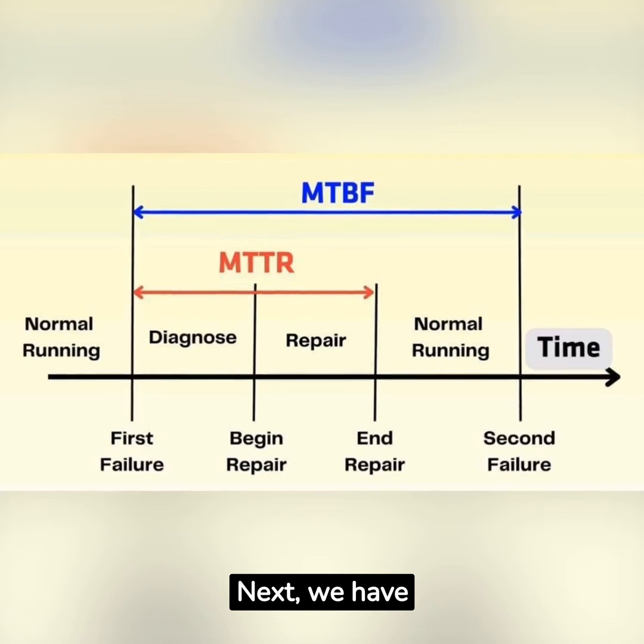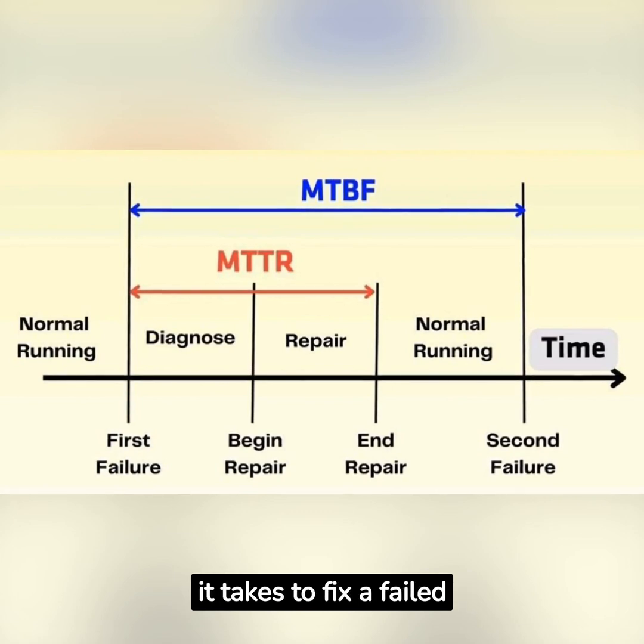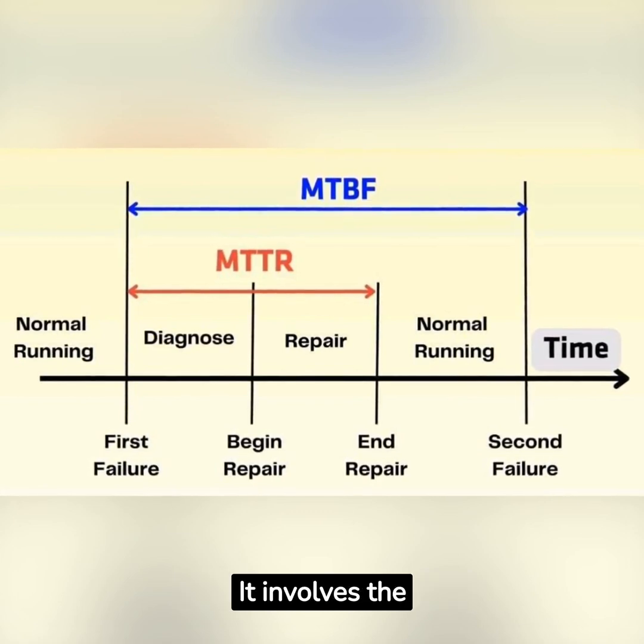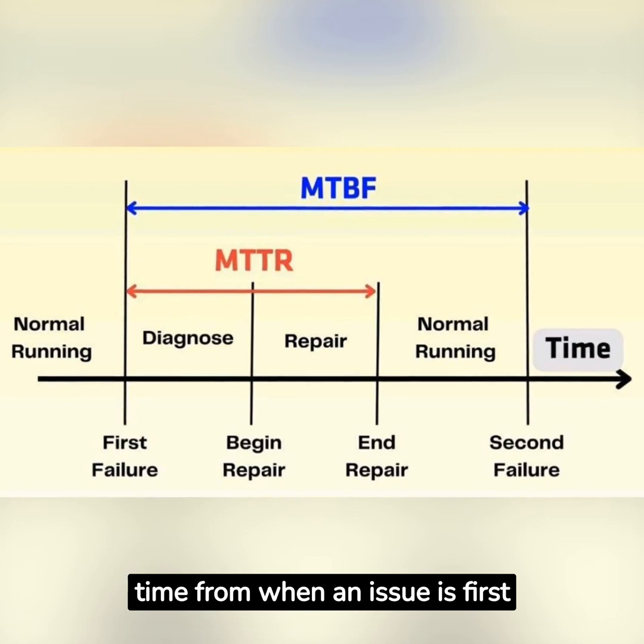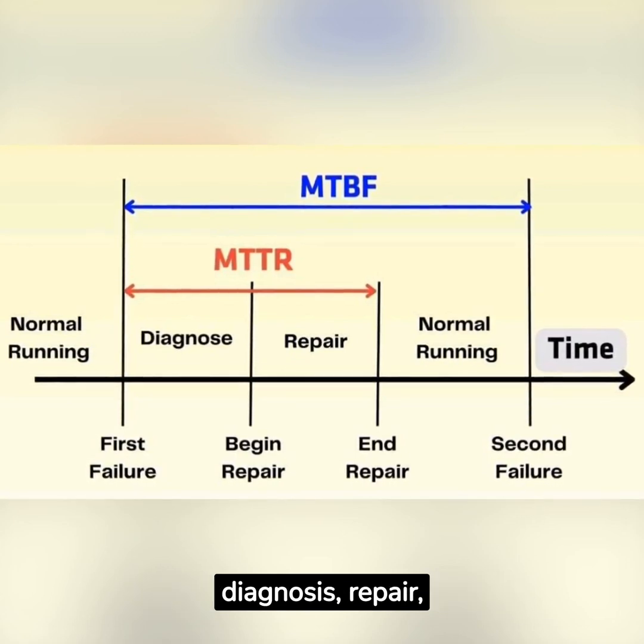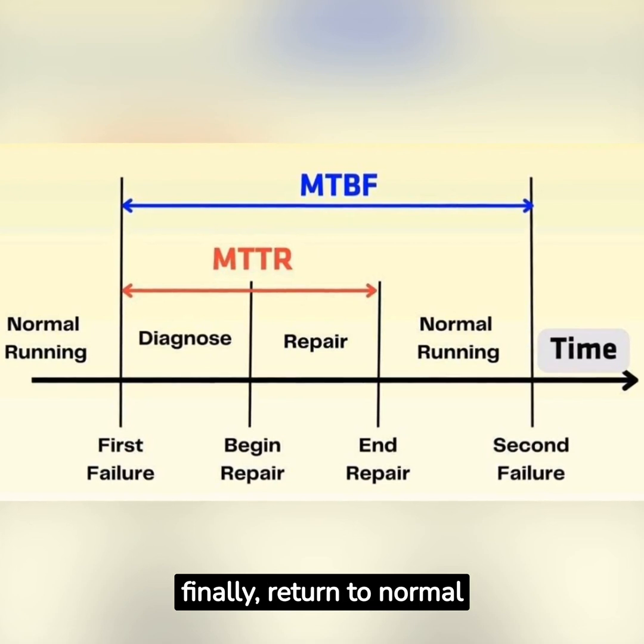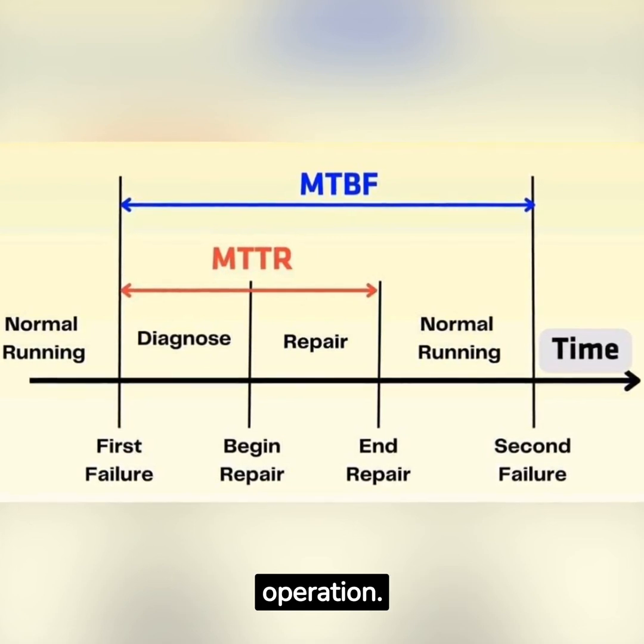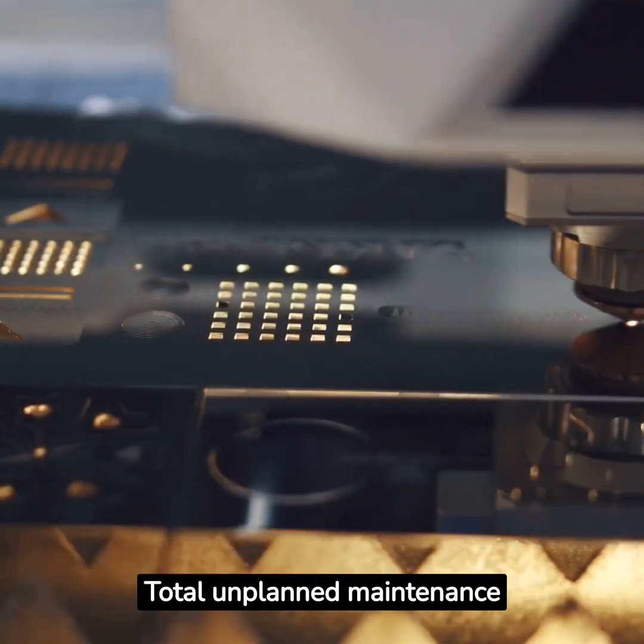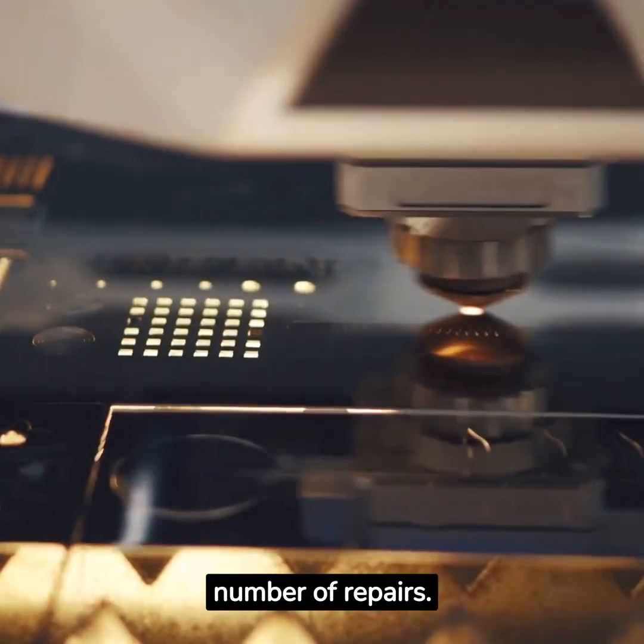Next, we have MTTR, or mean time to repair. This is the average time it takes to fix a failed component or system. It involves the time from when an issue is first identified, through diagnosis, repair, testing, and finally return to normal operation. MTTR is total unplanned maintenance time divided by total number of repairs.